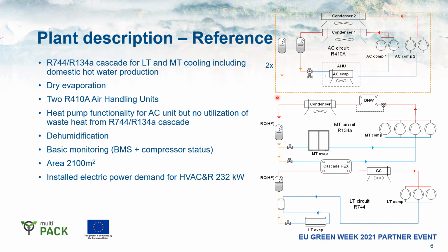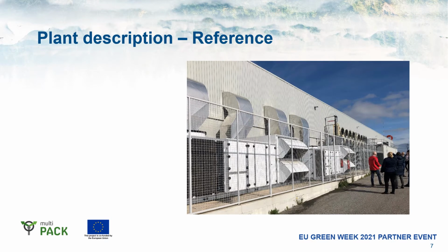They have a dehumidification function, and data acquisition of the system is basically done based on the basic building management system and the compressor status, which we get from the control of the refrigeration system. The shop area is comparable, in the order of 2,100 square meters, and the installed electric power demand for the HVAC and R system is about 230 kilowatts. If we look outside the shop, we see on the left the two air handling units placed beside each other, while the machine room is at the complete end, and the condenser of the R134a units is seen hanging on the outside of the south wall.